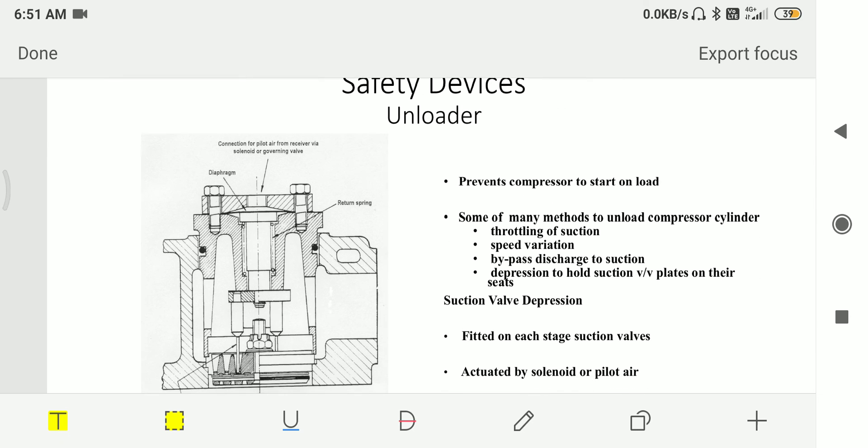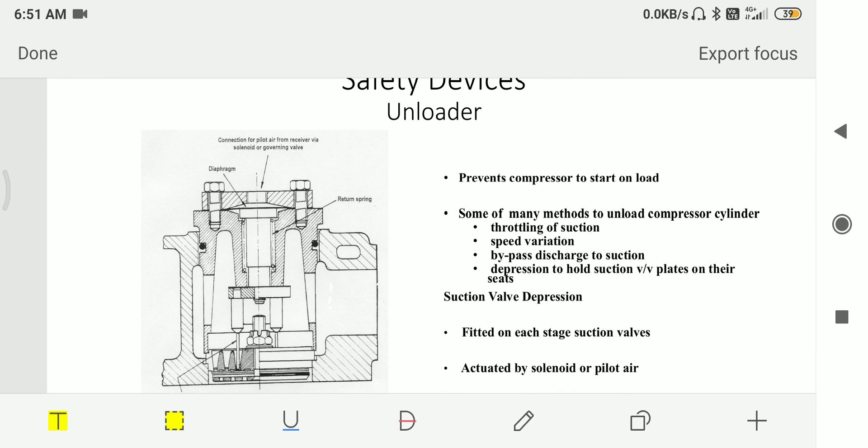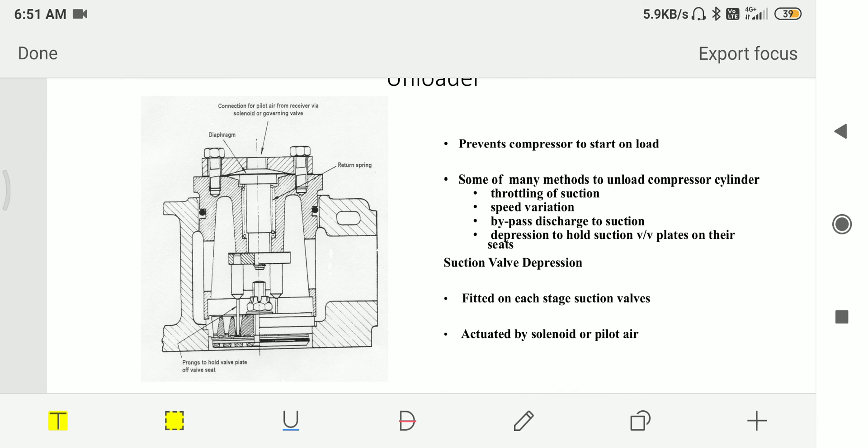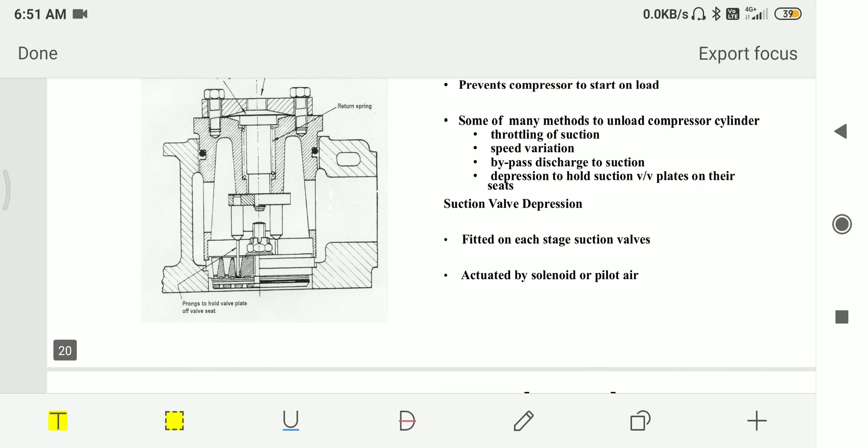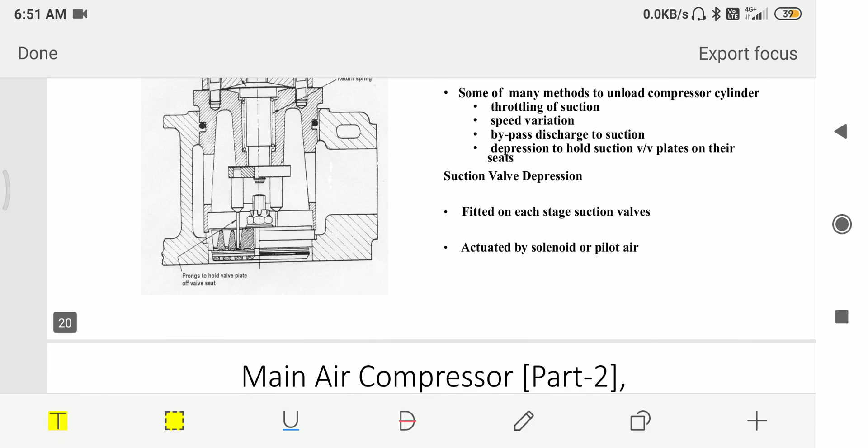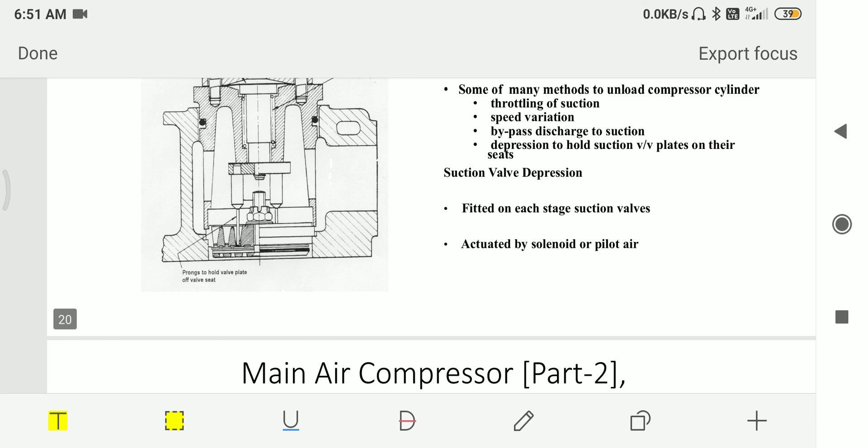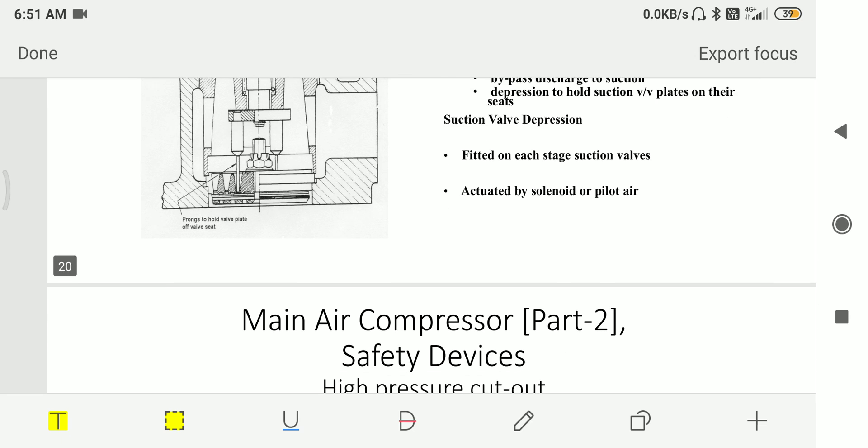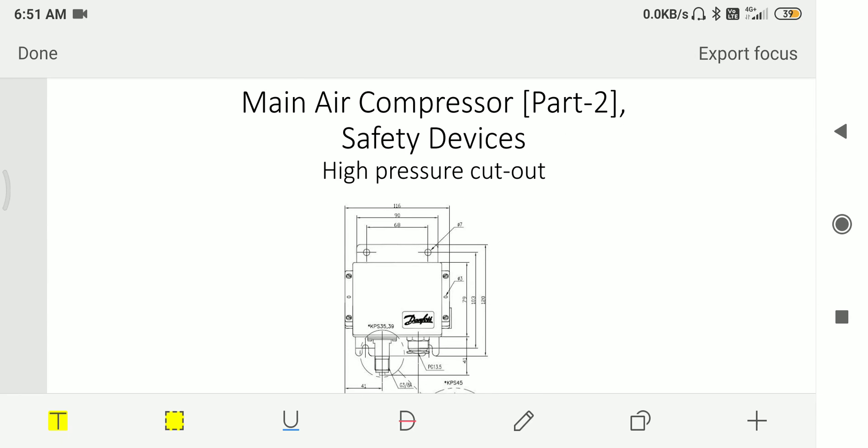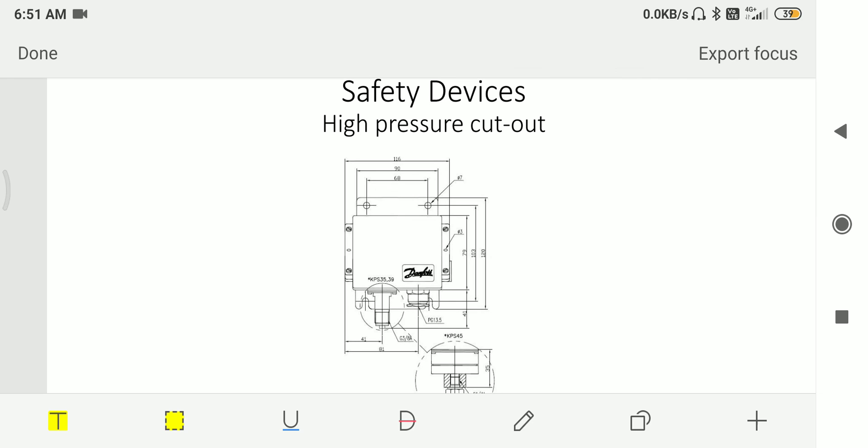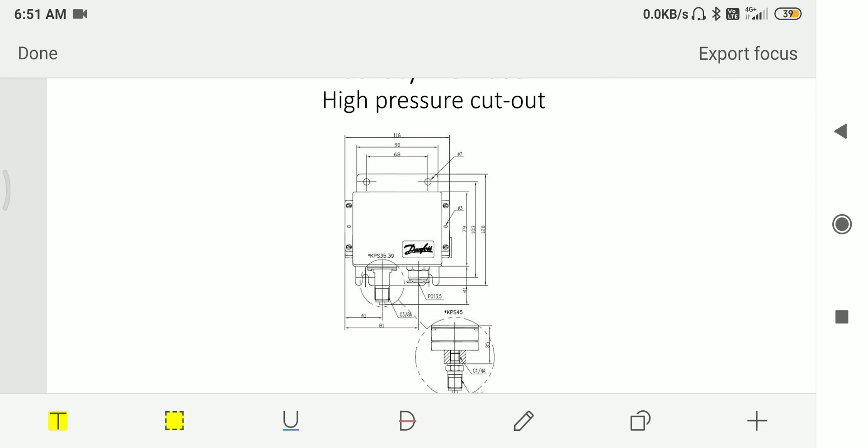Then we have unloader that prevents compressor to start on load. Some of the methods to unload the compressor are throttling of the suction, speed variation, bypass discharge to suction, and depressing to hold the valves on their seats. These are fitted on each stage suction valve, actuated by solenoid or pilot air.